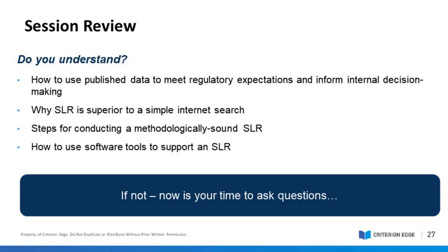No, it's not mandatory to prove equivalence for other comparator devices or other devices found in clinical literature. The only time it's mandatory to prove equivalence is if you are taking the equivalence route to establish the safety and performance of your own device.